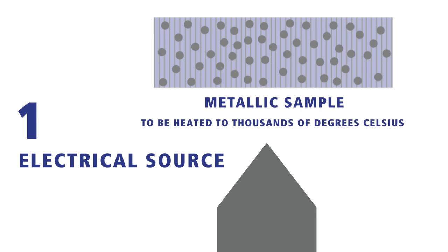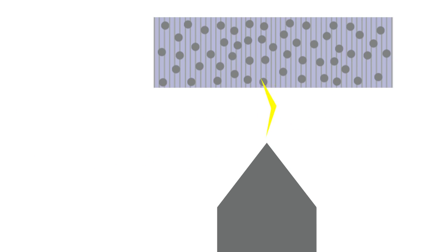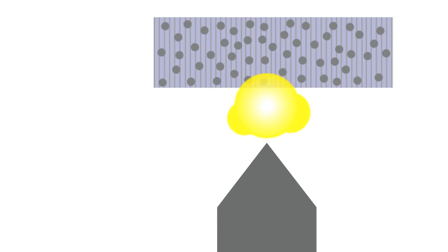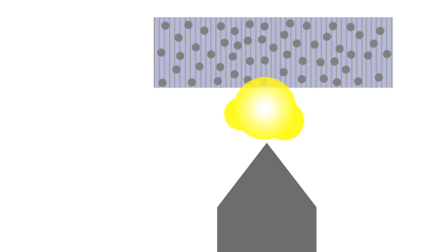This is done using an electrical high voltage source in the spectrometer via an electrode. The difference in electrical potential between the sample and electrode produces an electrical discharge. This discharge passes through the sample, heating and vaporizing the material at the surface and exciting the atoms, which then emit element-characteristic emission lines.